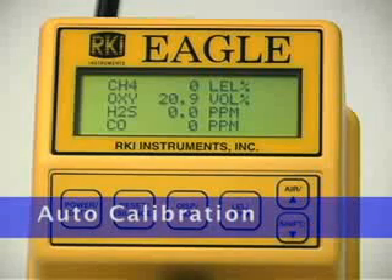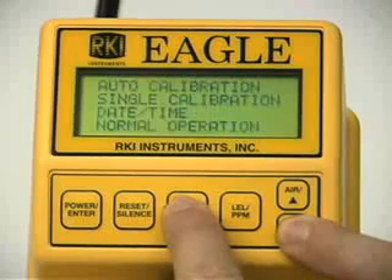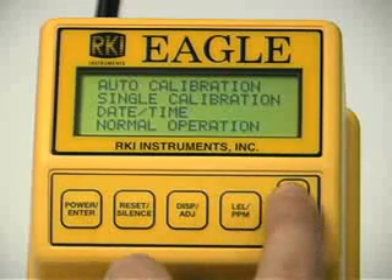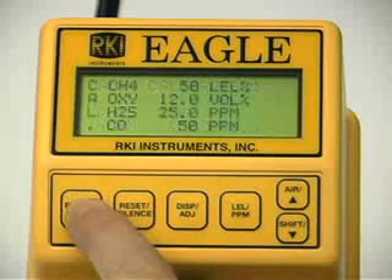To enter the calibration menu, press and hold the shift down button, then simultaneously press the display adjust button. Your EAGLE may display slightly different gases depending upon your EAGLE's configuration. To calibrate using the auto calibration method, use the up or down button to place the prompt next to the auto calibration menu option. Press the enter button to display the calibration values screen.